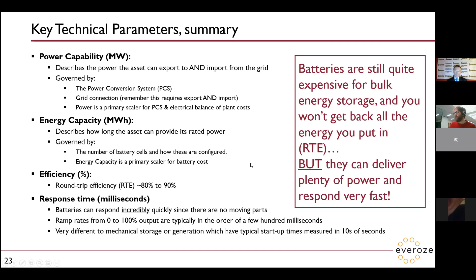Now, why is a battery like a bottle of tomato ketchup? Well, it's because you have to use it a lot slower, or pat the bottom as you usually do, to get it all out. So you might get a battery with a nameplate of 1 megawatt hour, but you're only necessarily going to get all of that if you use it at a low power. Say it's designed to operate at 1 megawatt - you probably wouldn't get your 1 megawatt hour if you're running it at that rate, but if you ran it at half or a quarter of that, you'll get a lot more energy out.